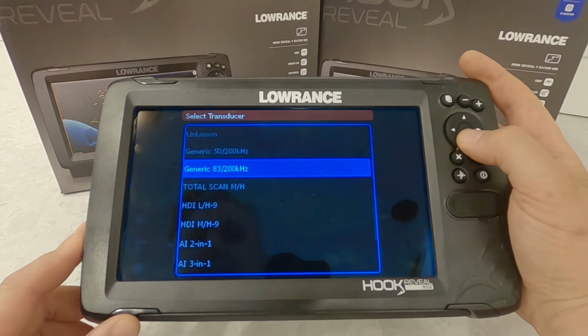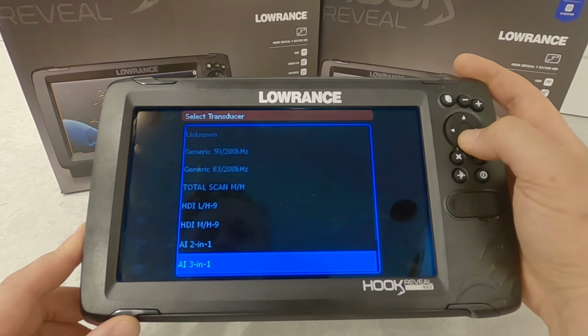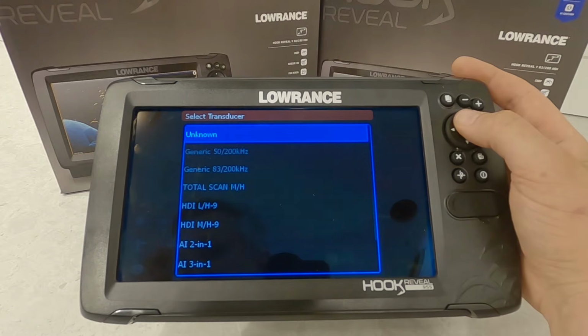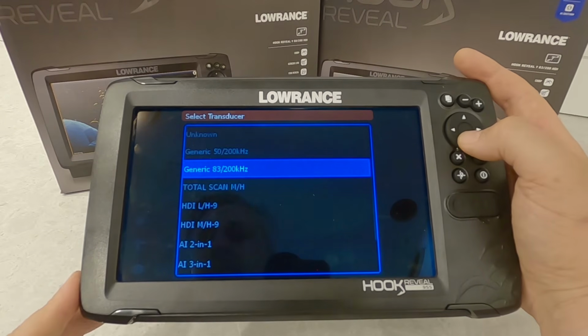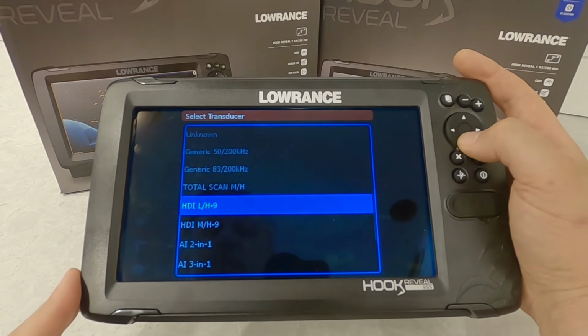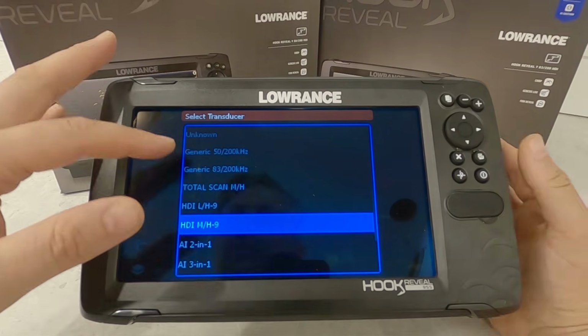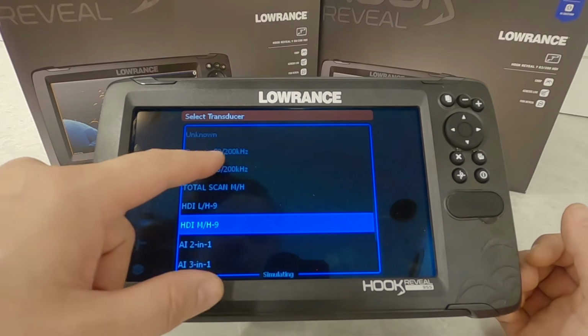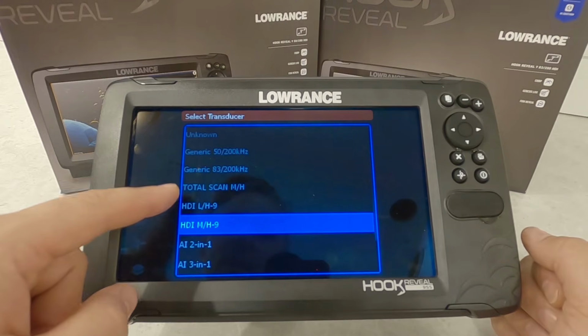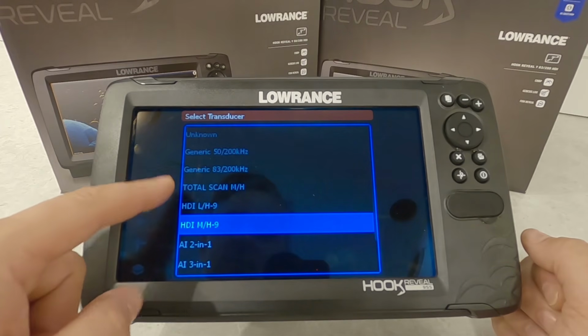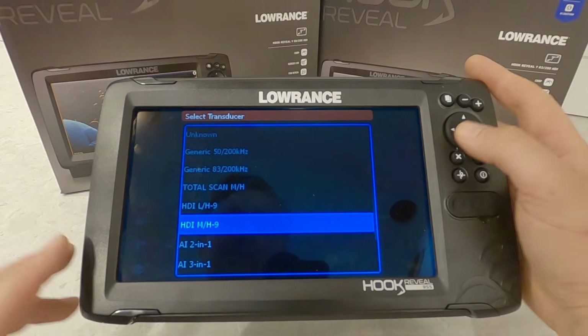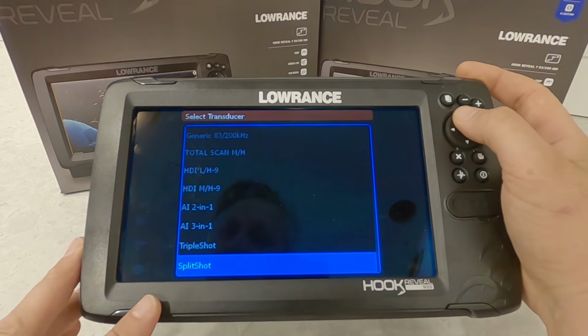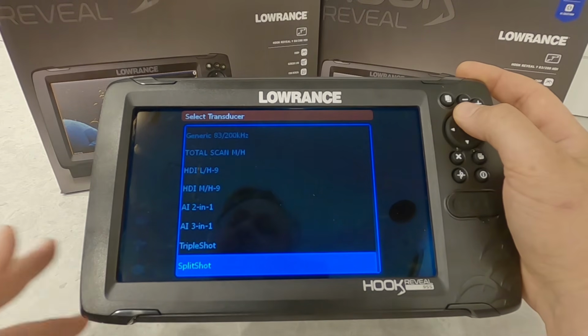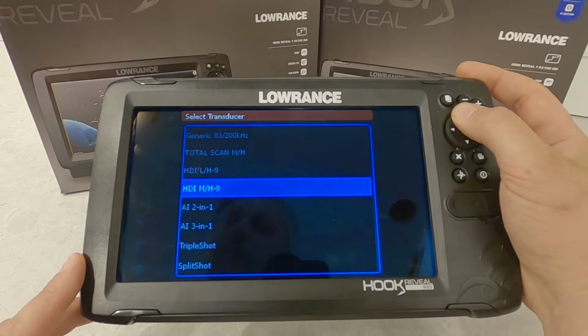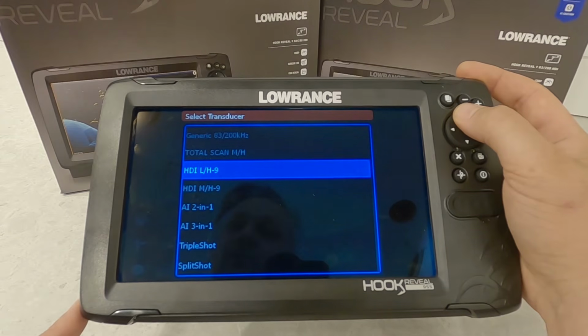In here, we can select the type of transducer we have. There are quite a few different transducers you can use with this unit. It should auto detect what's plugged in, but if it doesn't, you can manually select it. Generic is for when you don't know what you have but know the frequencies, select that. Otherwise try to get exactly what you have, whether it's a total scan, HDI, active imaging, triple shot or split shot. Selecting them properly limits the menu options to what's specific to the transducer that's plugged in.